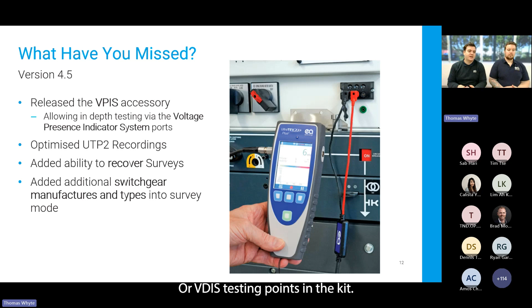It gives you a standardized test point and lets you test each individual phase separately, red, white, and blue, to earth. You get a really in-depth and granular display of what's going on within your switchgear. It works really well for main switchboards and for RMUs as well. We've got a lot of good data and really good feedback, and it's proving quite sensitive.